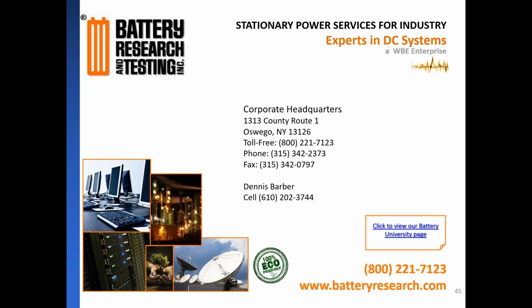That's usually an indication of an older unit. At that point, transformer replacement is usually rectifier replacement, unless you're talking a very large system. But if it's going to cost more, you might as well just replace the whole charger. Absolutely. If you're talking a 50 amp charger or smaller, and again, it depends on the age of it and warranty. A lot of times manufacturers will warranty the transformer. They may give a 10-year or 15-year warranty on the transformer just because they are so robust. They typically don't go bad. So that's something you may want to look at.